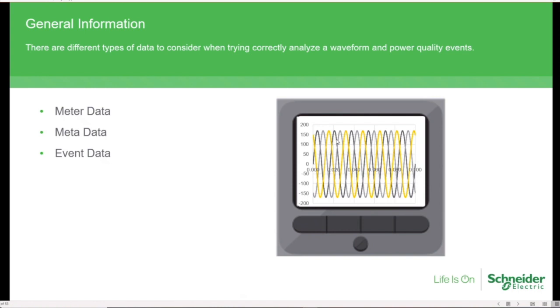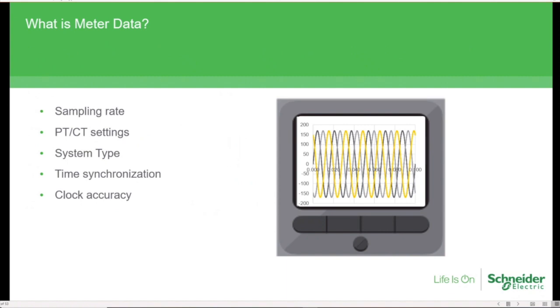So in the general information, there are three main categories: your meter data, the metadata, and then the event data. The meter data is information about the meter, and the sampling rate is a good example. The ION 8650A, B, and C has a sampling rate of 1,024 samples per cycle. That's the sampling rate the DSP works at.